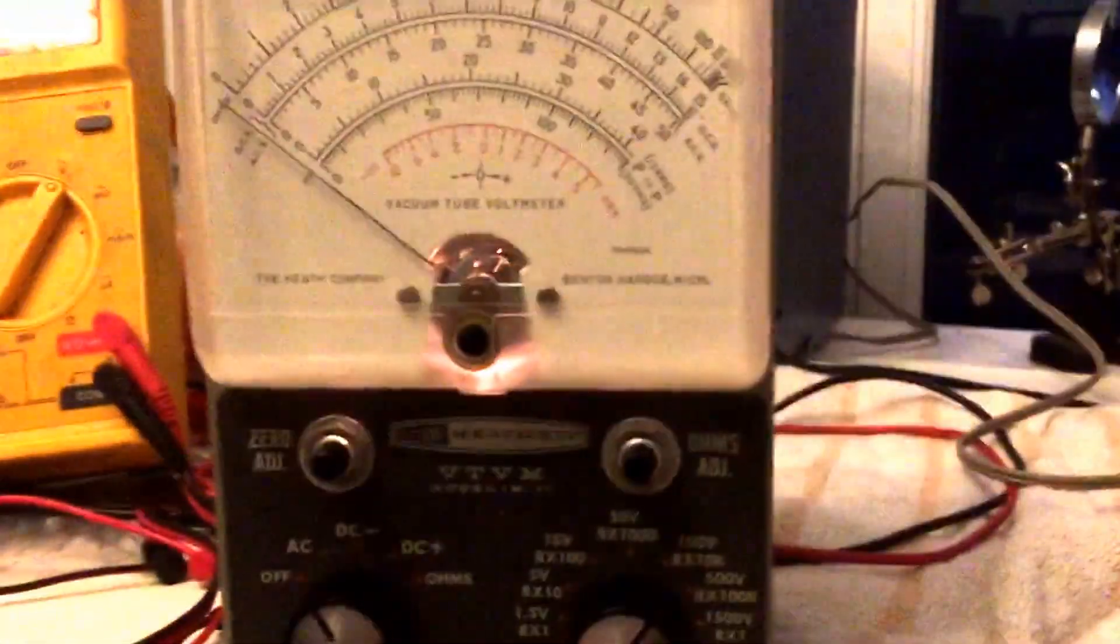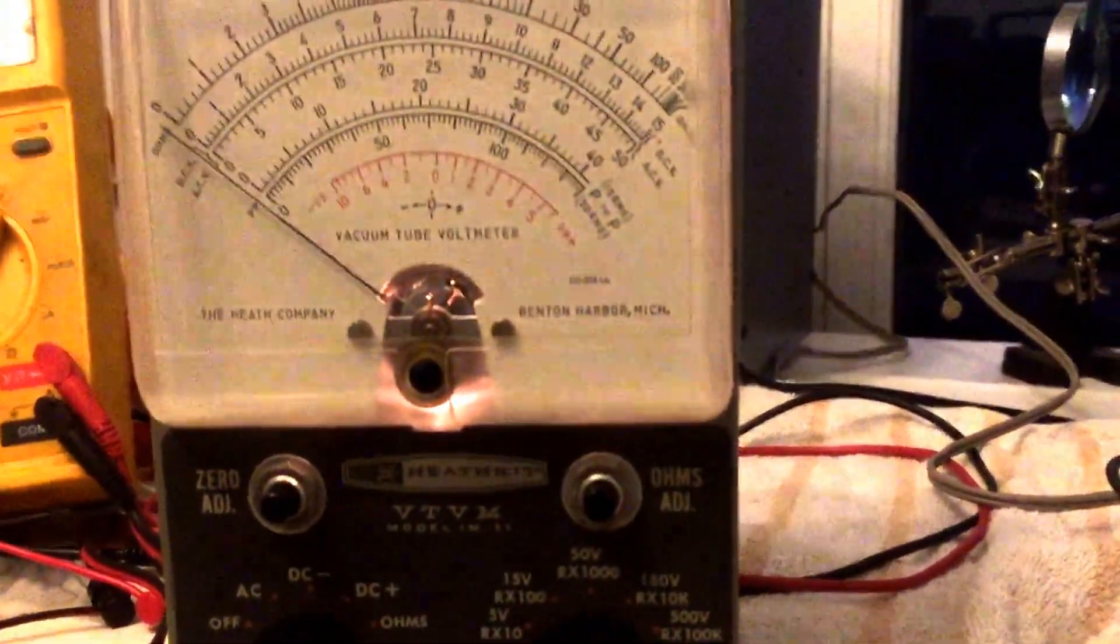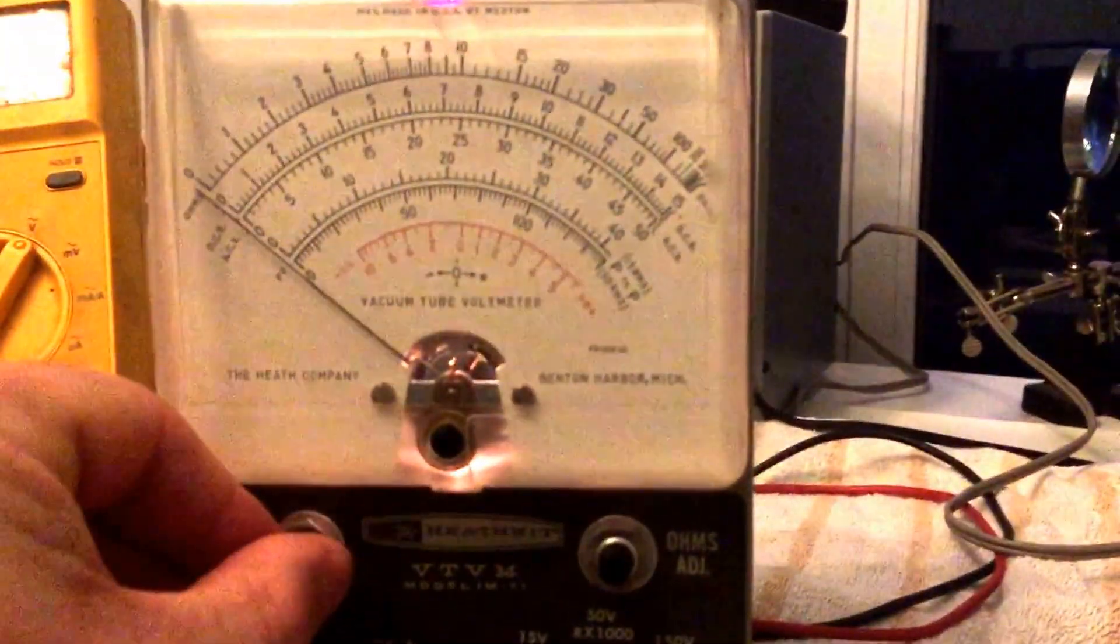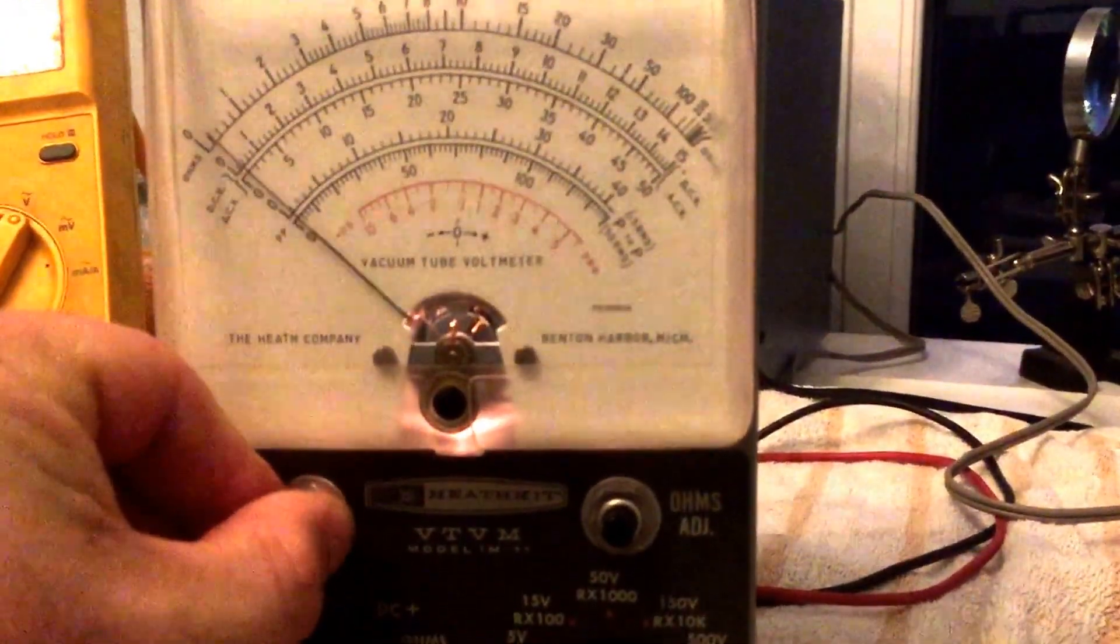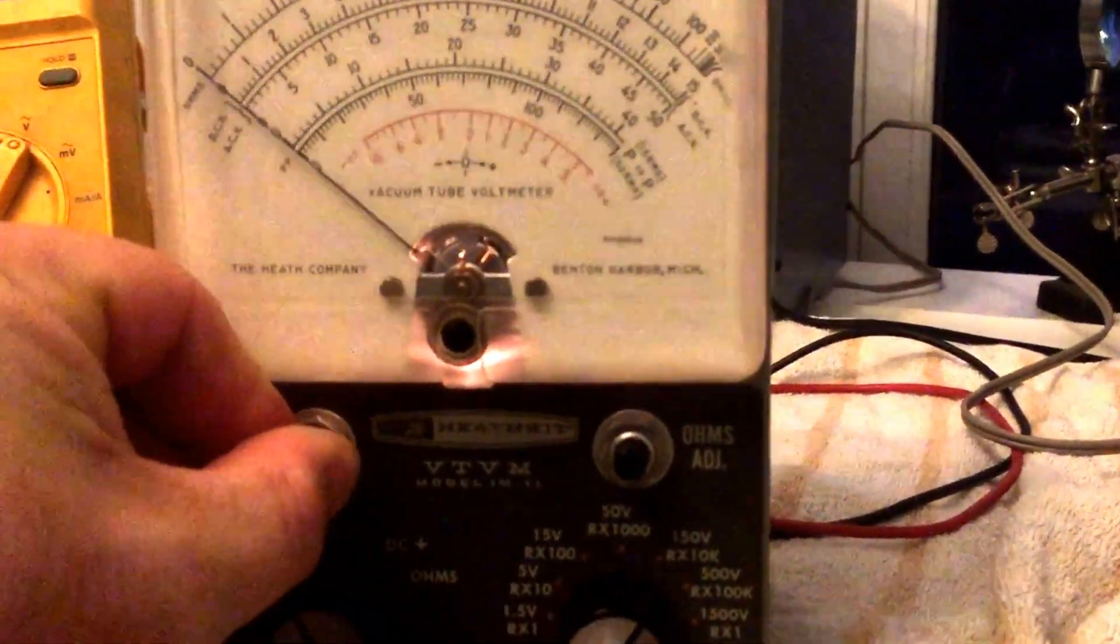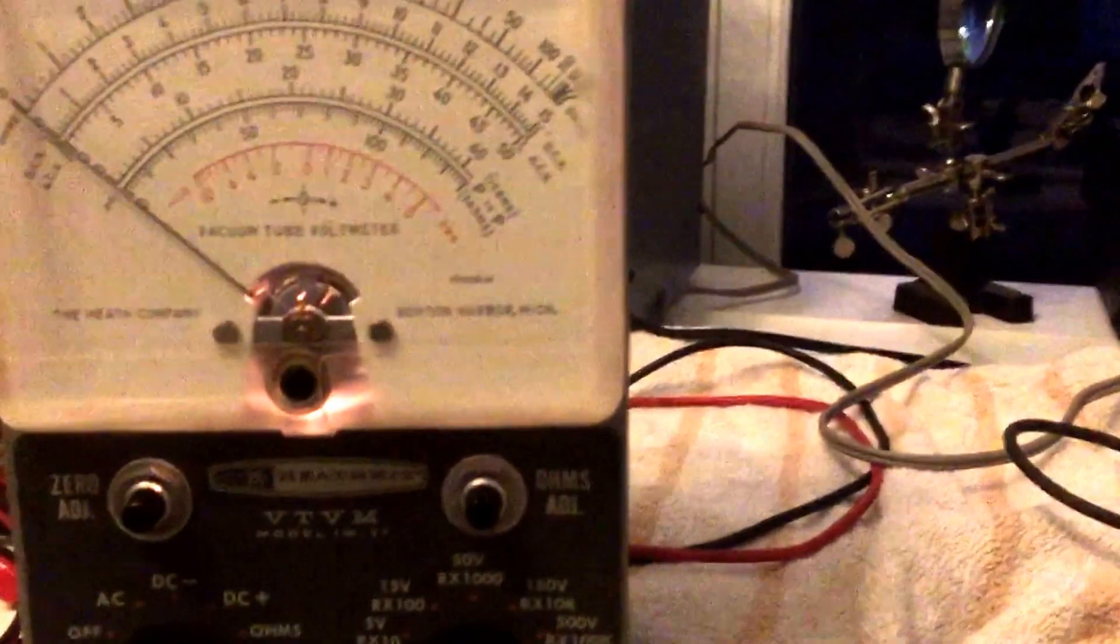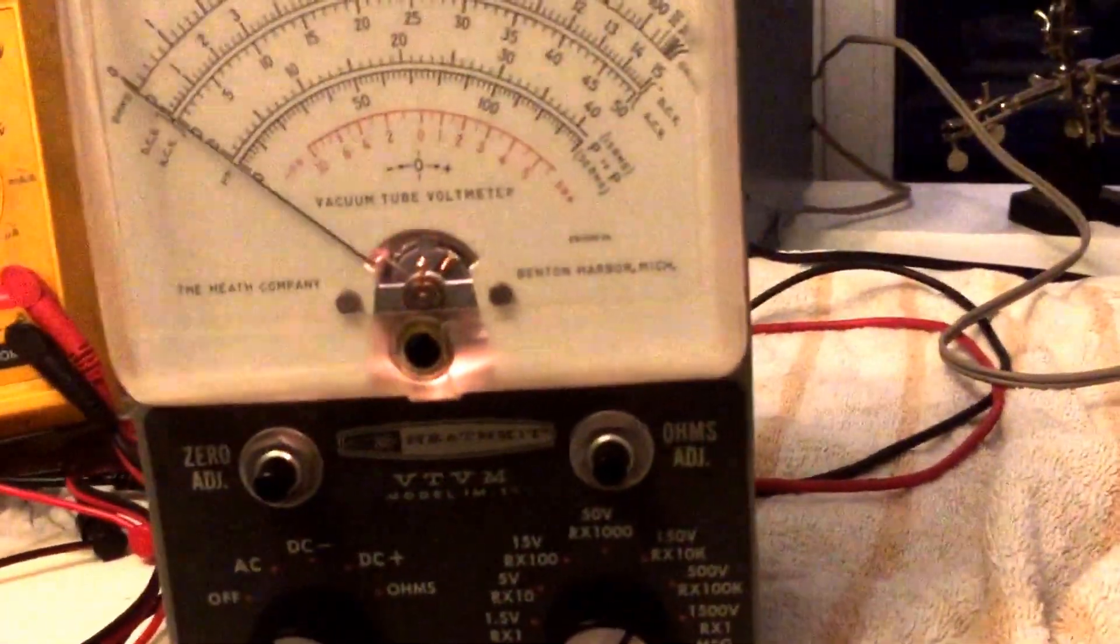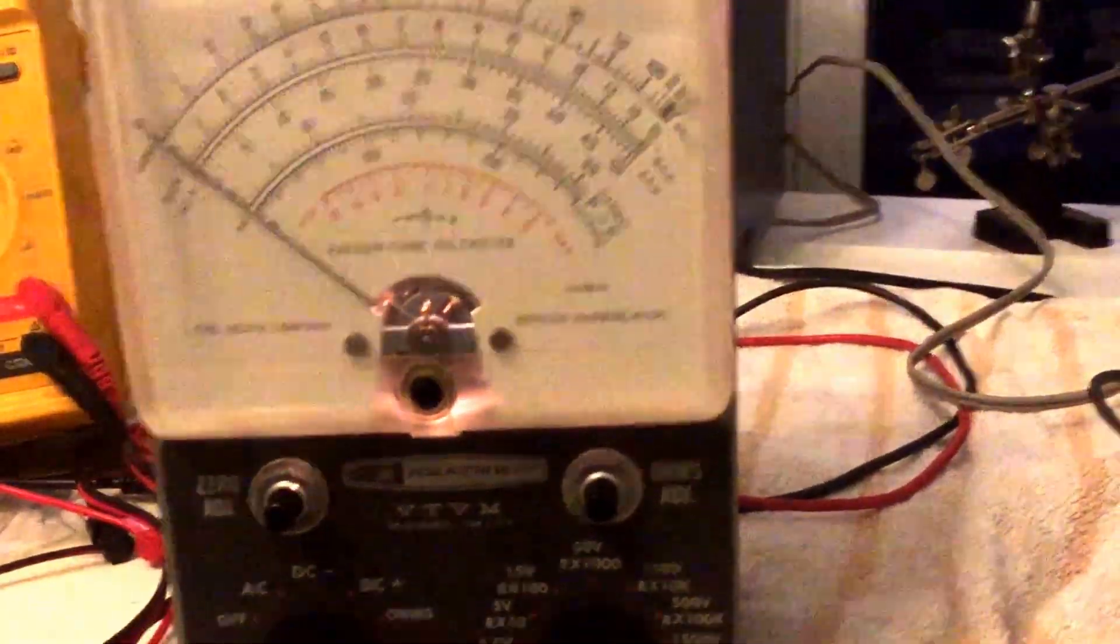There's three potentiometers in the back. A couple potentiometers in the back are used for AC/DC balance, AC calibrate, and DC. One of the things you're supposed to balance is the ability to go from AC to DC with little or no deflection.